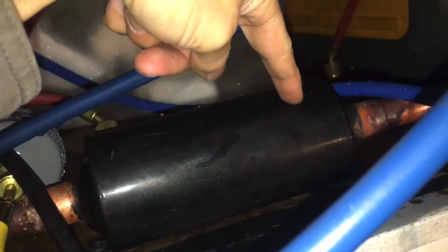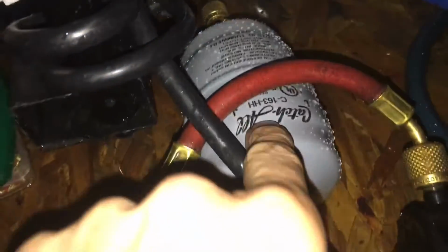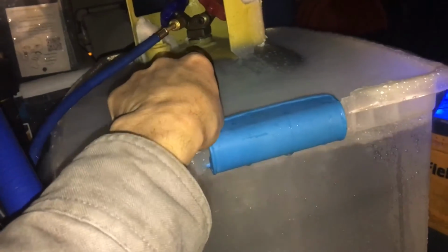But even though, just in case, on my outlet, I'm hooked up to the low side, the high side, and I have them reversed. Coming down, I'm going through an HH filter. Then it goes through the HH filter, you know, high moisture capacity, goes into the recovery unit. Then it comes out of the recovery right here, and it goes through another HH filter right there. So we're going through 163 HH, and then it's going back into the container.